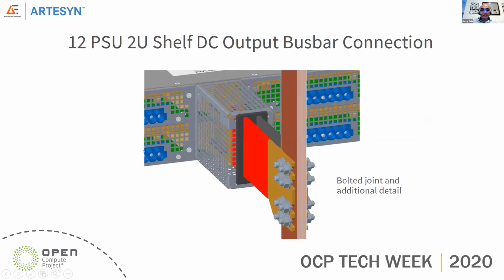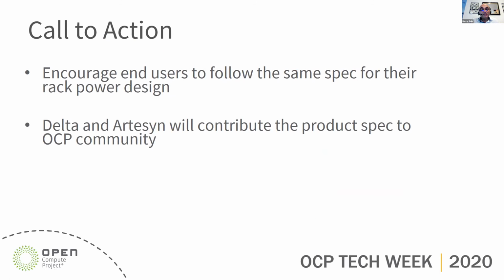Moving on finally to the shelf DC output bus bar connection. Again, we need to emphasize here you're getting a complete view of the AC input connectors and the bus bars, and exactly how the bolted joints and this connection is implemented to get the minimum possible impedance and optimize the shelf design. That pretty much completes the aspect of the Artesyn design PowerShelf.